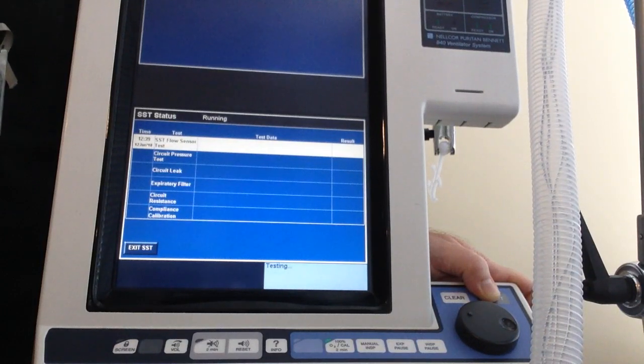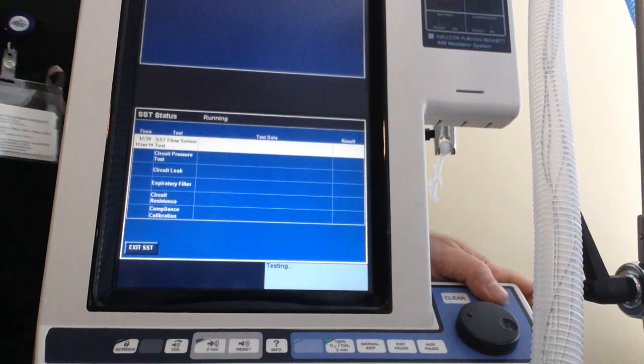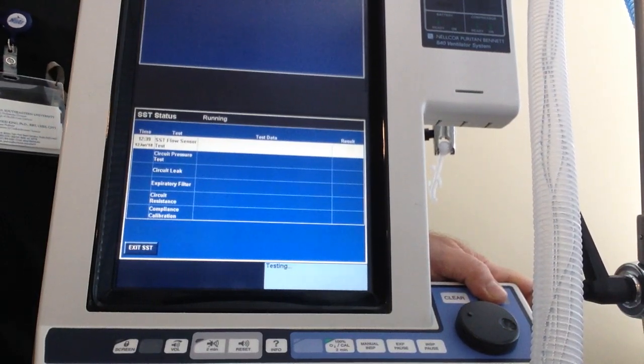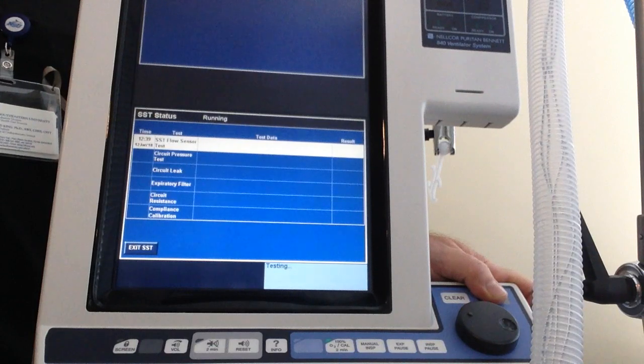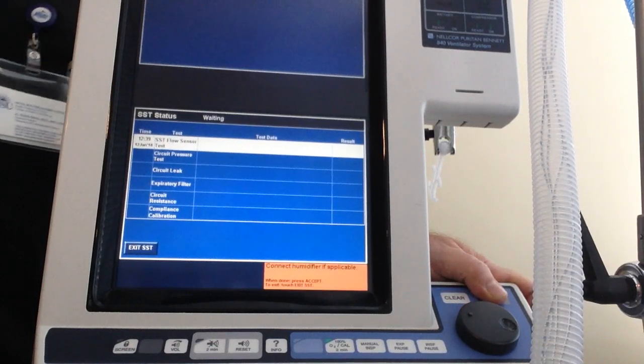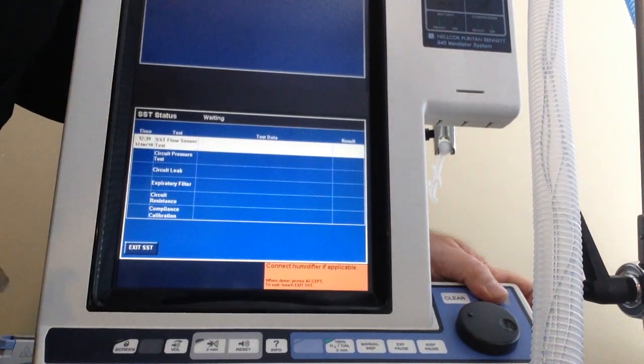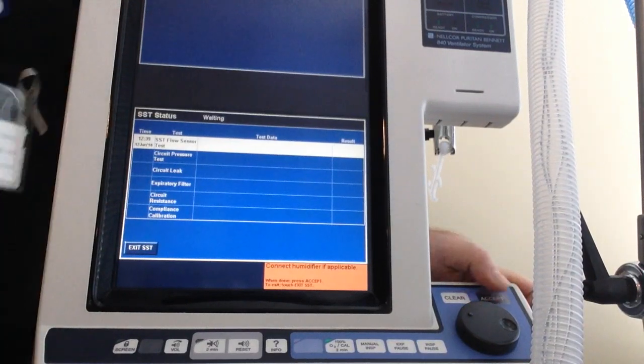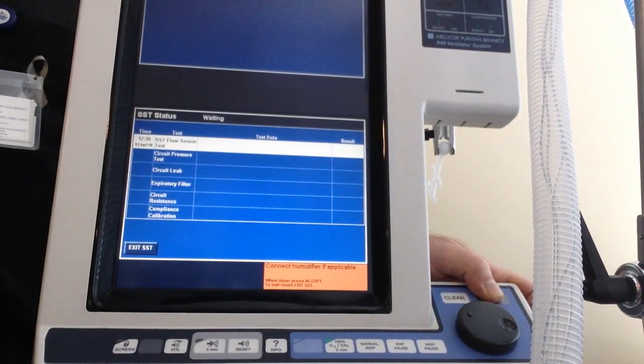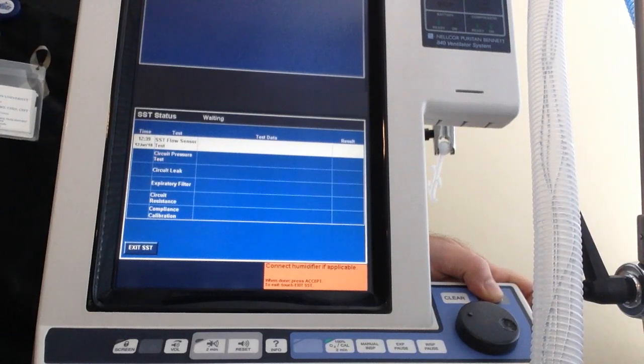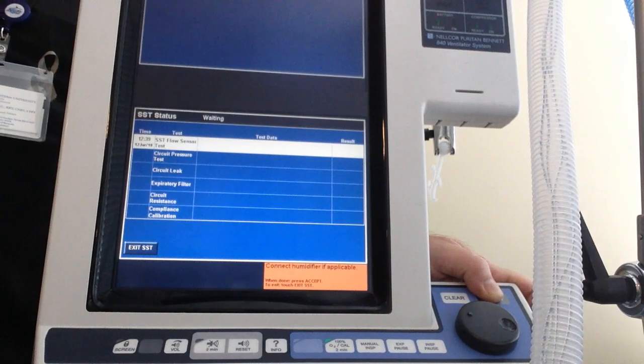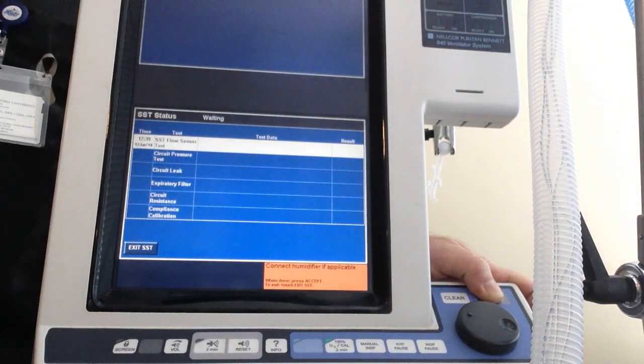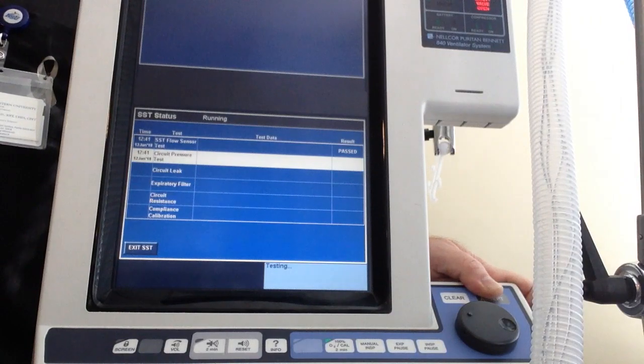This is just a waiting game, and the machine will prompt you through every step. The Servo-i does the same thing. All of them will prompt you, and you basically read the screen. Okay, it says to connect humidifier if applicable. We have already connected it. This would be if you have an HME that you want to put in line. Ours have a twist, so they tend to leak. So we're just going to accept that our HME is already in line.